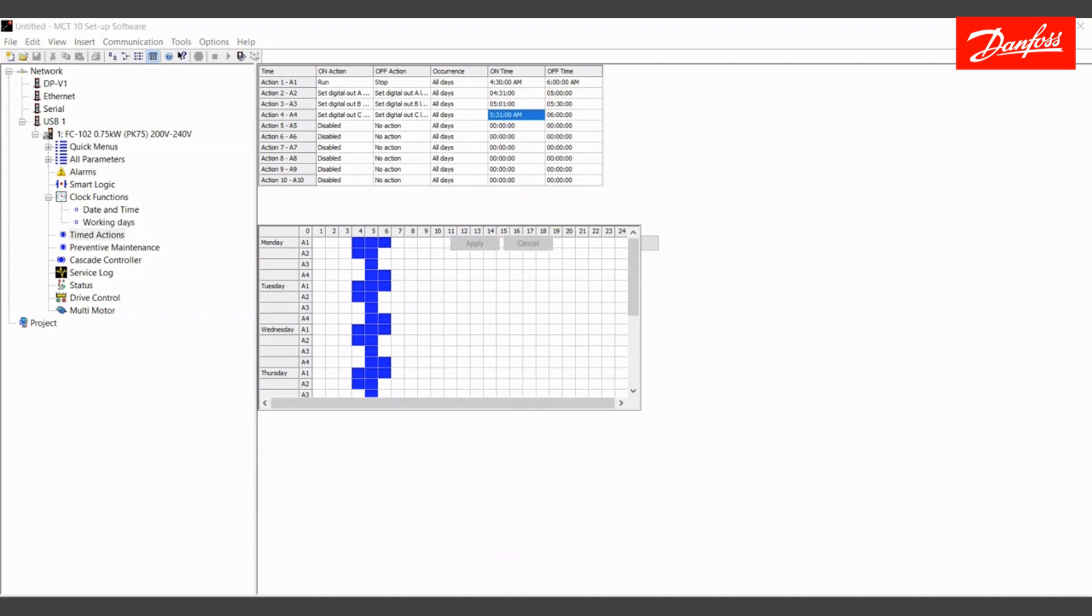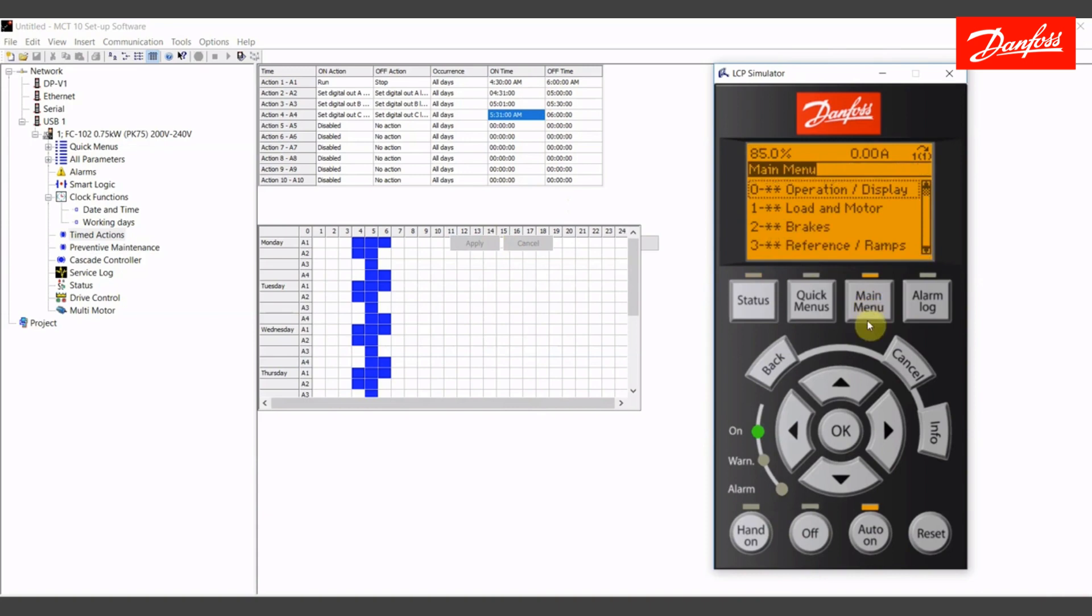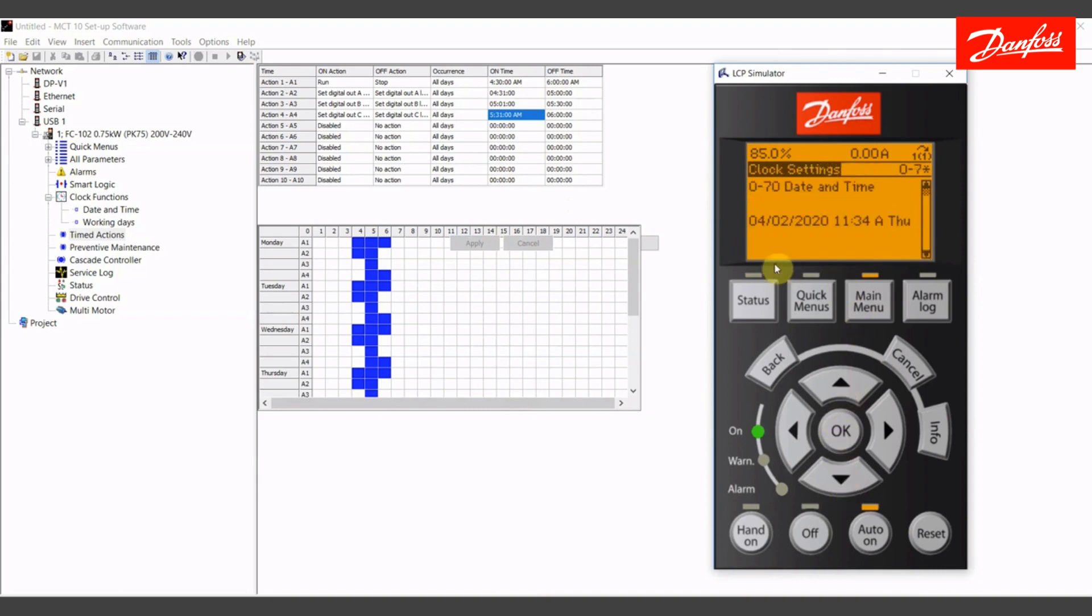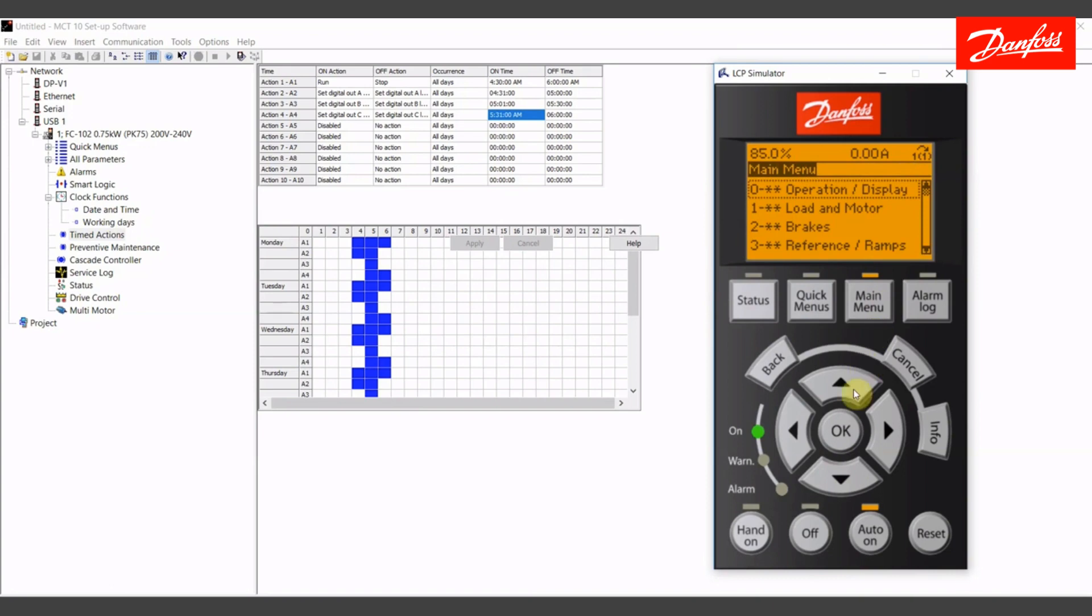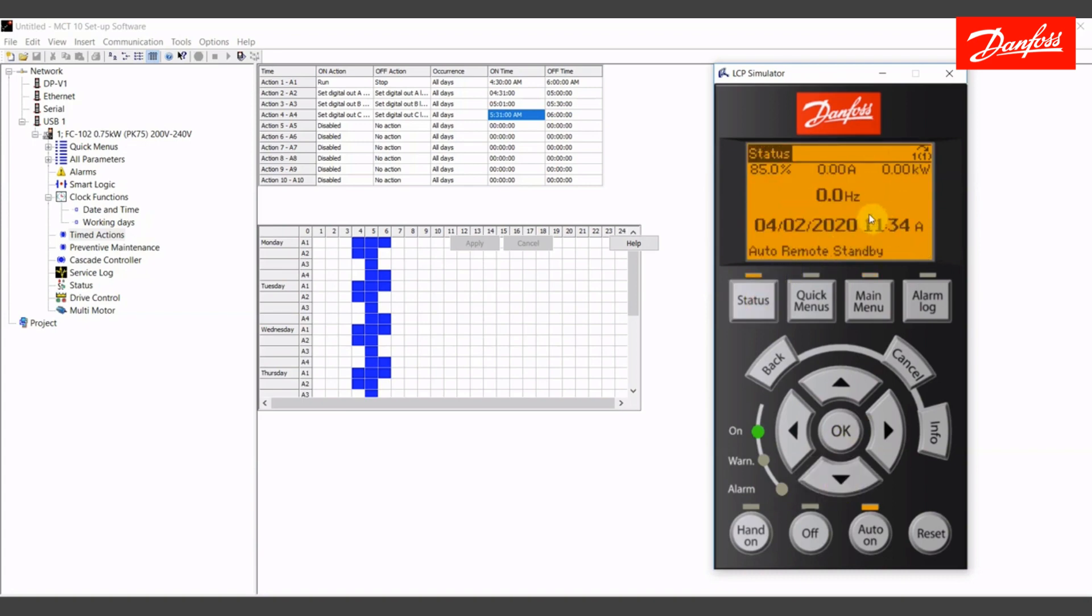I'm going to pull up my keypad simulator here. I have set it to display the actual time of day. To do that, you'll actually do it in the zero parameter groups. You set the clock in parameter 070. I've already done it with the MCT10 wizard. And if I want to display that clock, you'll do that in 0-2 LCP display. I currently have large line three to show the date and time readout, which is why we see it here.